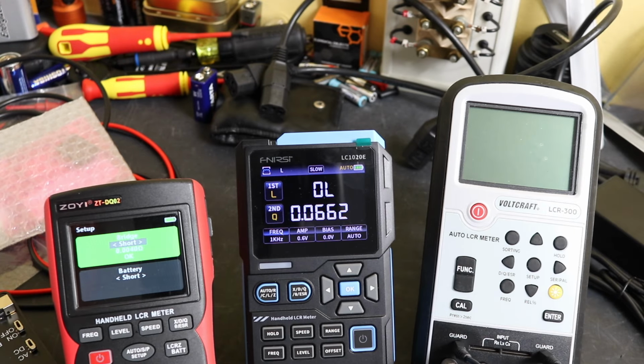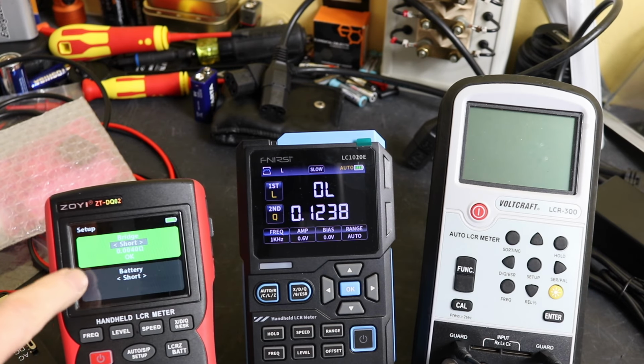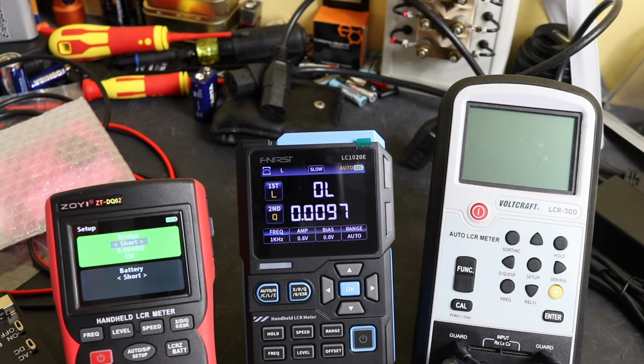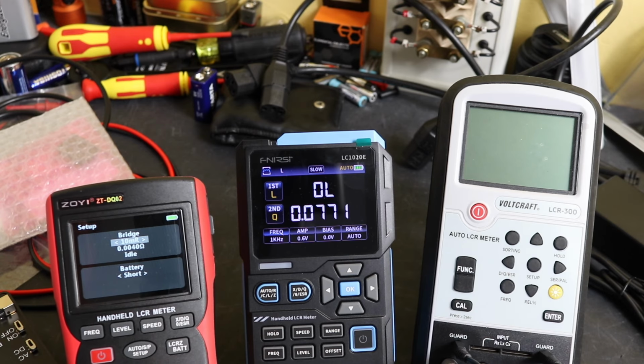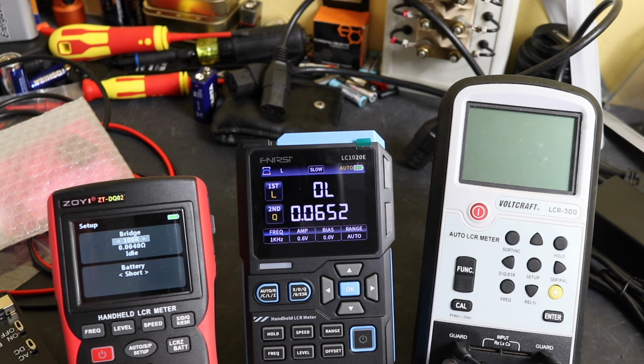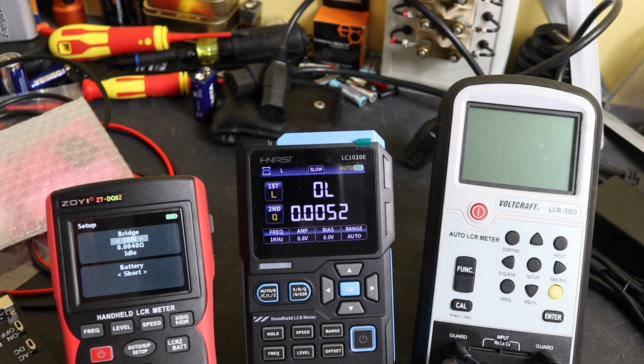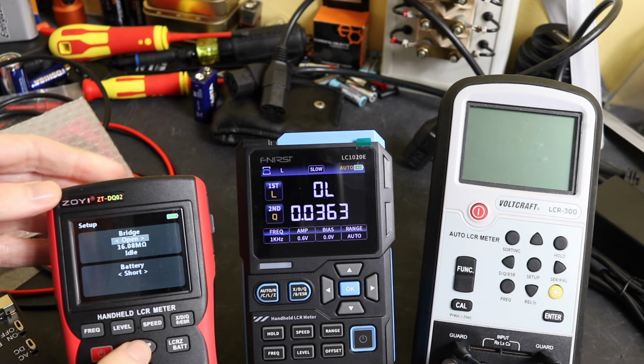So we can do a calibration in a similar manner with the Zoyi unit. This is our short that we've set up here. It runs through it and it said it's okay. You can actually put in more values for this one. You can test the bridge to 10 milliohms, 100, 1 ohm, 10R, 100R, 1K, 10K, 100K, 1 megaohm, 10 megaohm, and then finally our open, which we can do again.